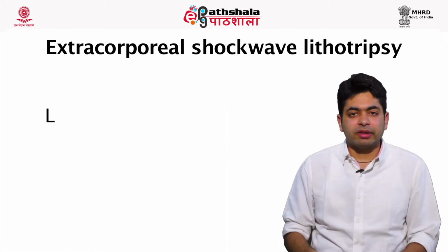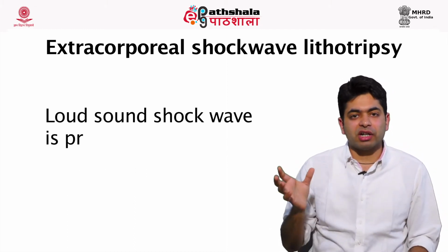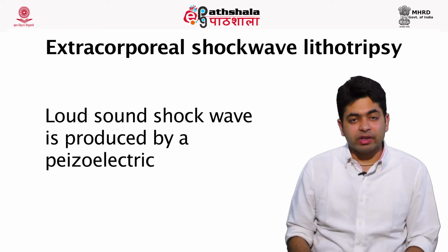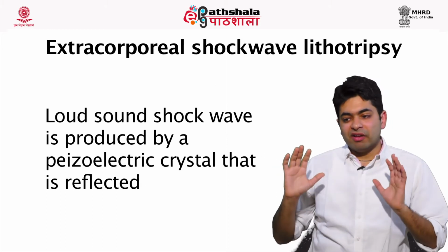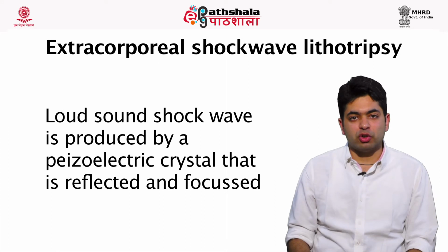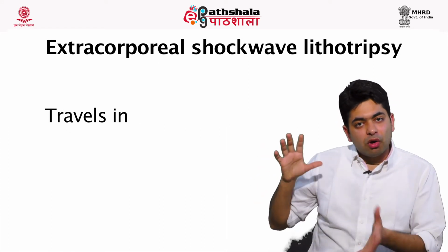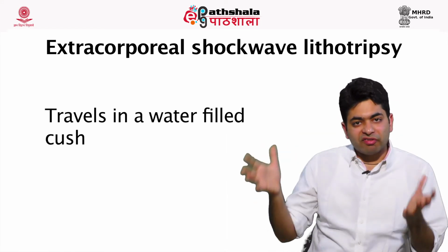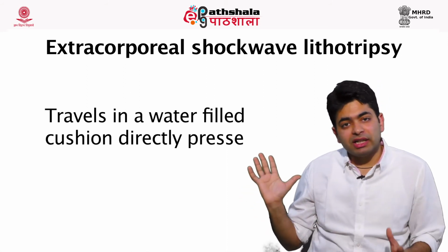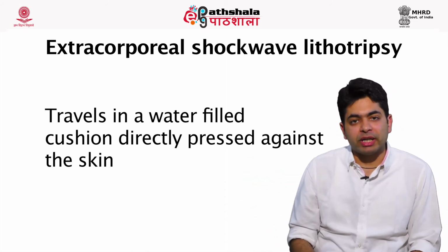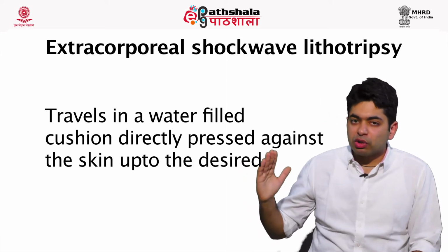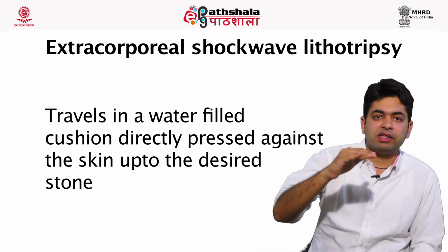So the mechanism is, again, there is a piezoelectric crystal which converts the electrical energy into sound waves. Then there are multiple reflectors which focus these sound waves towards the human body. All this apparatus is located in a water filled cushion. That water filled cushion is in complete contact with the human body. So the sound waves start to travel in the water and then start to travel in the human body.